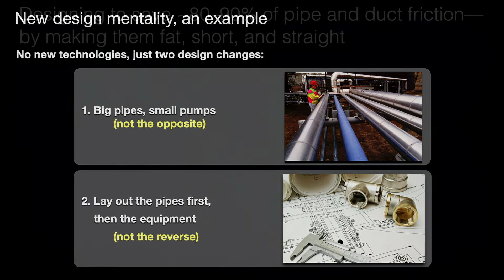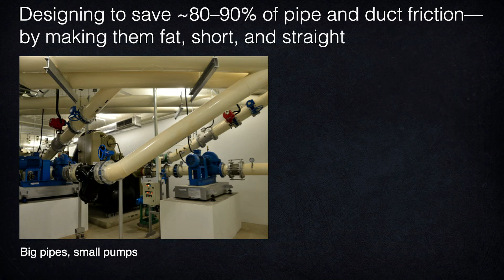You'll notice we raised the pump up on a plinth to meet the pipe, rather than traditionally dropping the pipe down to the pump on the floor and back up again with lots of right-angle bends. And the 10 chillers here, normally in a neat row, are staggered to eliminate pipe elbows.